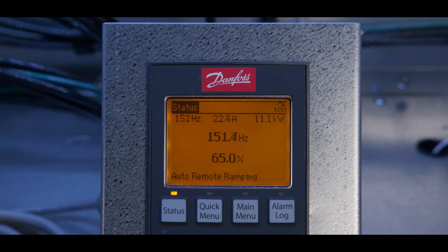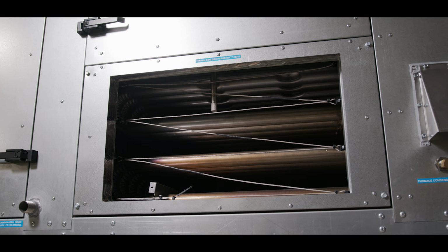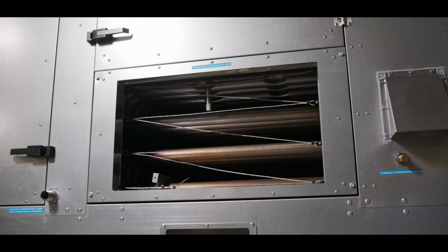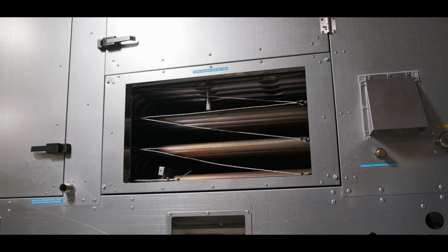We have to control every one of these components in the system, and there's a specific guideline for every component on how you write that PID loop and how you control them, how many times you cycle them on and off in an hour, and how you bring oil back to the different systems. All of that has to be researched, and we have to do it the correct way to maintain that quality standard.